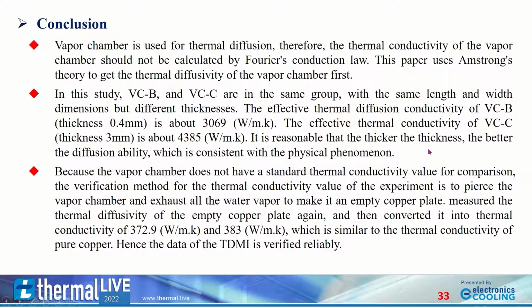Measure the thermal diffusivity of the empty copper plate again, and then convert it into thermal conductivity of 372 and 383, which is similar to the thermal conductivity of pure copper. Hence, the data of the TDMI is very reliable.